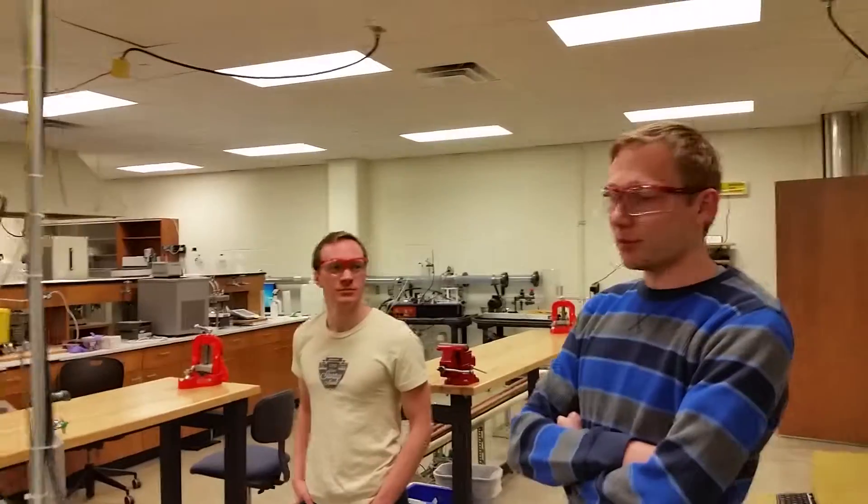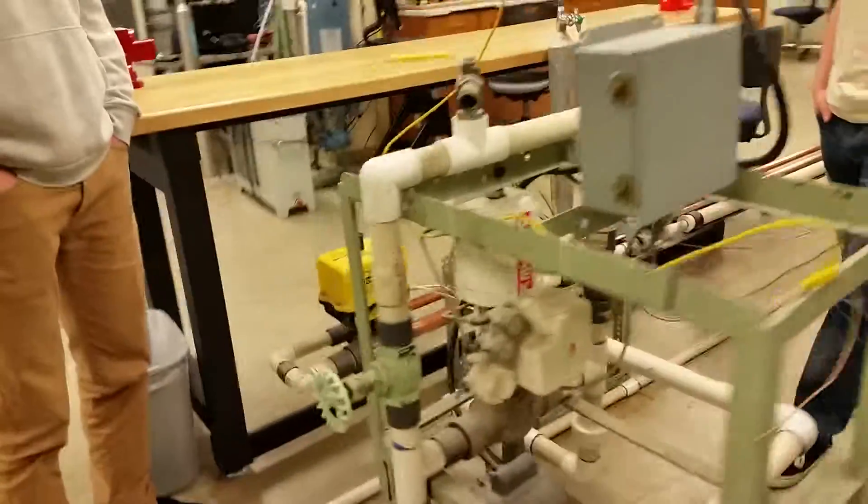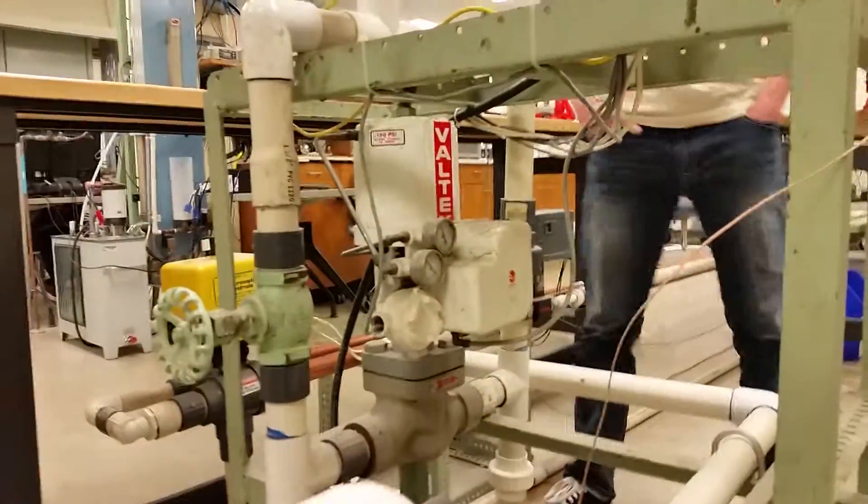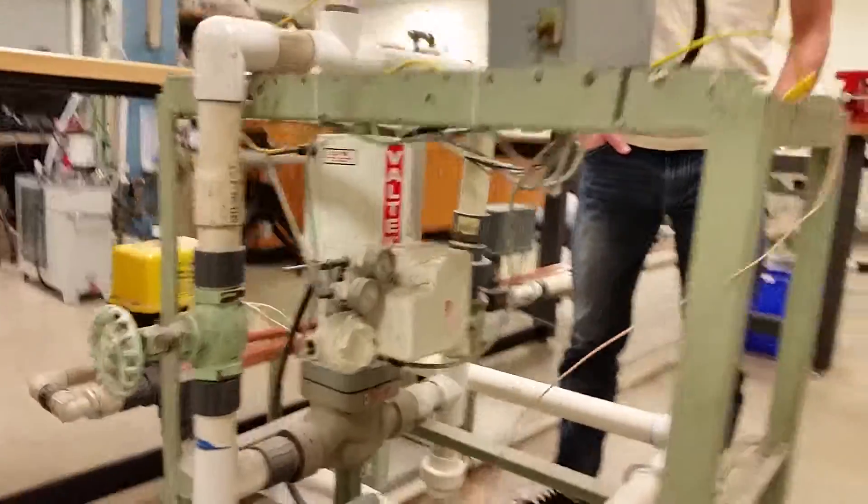Any other tricks or things? This is really helpful. One thing to know is that below 30% of the actuator, so the actuator by the way is this one right here, it's a pneumatic actuator for the valve. Once you get to operate on the little controller that they have in the computer, below 30%, it will start going to zero. And so you want to watch out as you get closer to 30%, it's going to start cutting off the flow rate to zero.